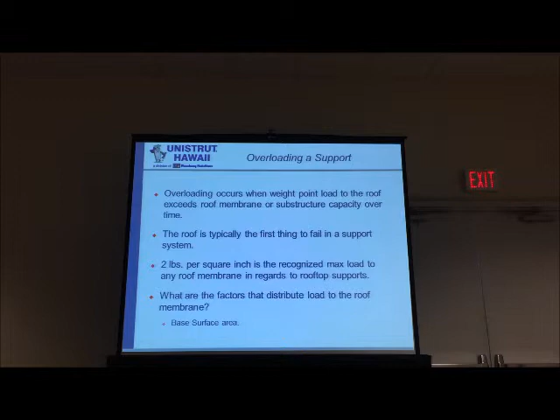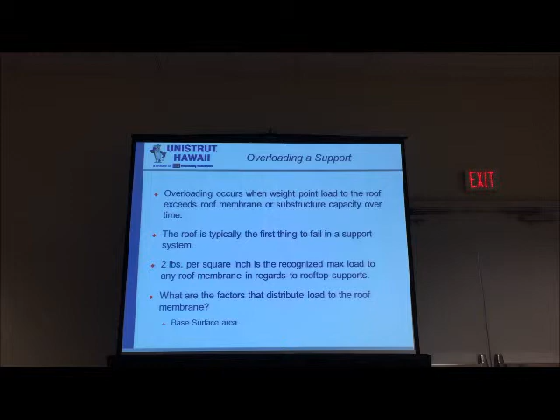Here we're showing that 2 pounds per square inch is the recognized max load any roof membrane can handle in regards to rooftop supports. Again, it's a simple mathematical calculation. You just have to understand your loading, how much surface area you have on your leg or support, and make sure you have enough bases and enough supports to divide that load to where we get to that number of 2 pounds per square inch.